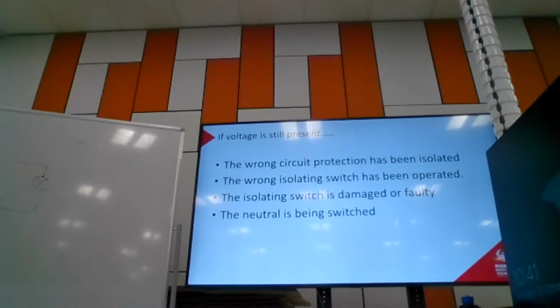Depending on how you test it, you may not even pick that up, right? So if I were testing phase to neutral here, and I've switched the neutral, it's going to look like 0 volts. Ideally, I'd be testing from there to there. And then even if I've switched that, I'm still going to show voltage, right? Because I've switched the neutral instead of the phase. That makes sense. So when I've switched off the circuit breaker or isolating switch or whatever, I've switched the neutral instead of the phase, I'm still going to show 230 volts even though I've switched it off.